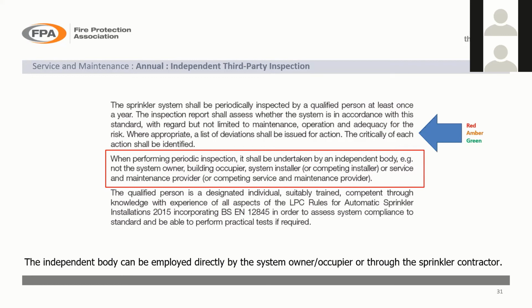The insurer aspect is that insurers do a great job checking the buildings, but they're not necessarily checking everything on the sprinklers in as much depth as an independent third party inspection of a sprinkler system. Also, if they see something that doesn't comply fully with the rules, they can take a view on whether to charge the full premium, or perhaps increase the premiums, or come to some agreement with the user. Whereas the independent third party is looking at: does it comply? If it doesn't comply, why doesn't it comply? And what is the criticality of that? So it's very important that you get your third party independent inspections carried out on an annual basis, and that is a requirement of clause 21 of BS EN 12845 and TB 203.